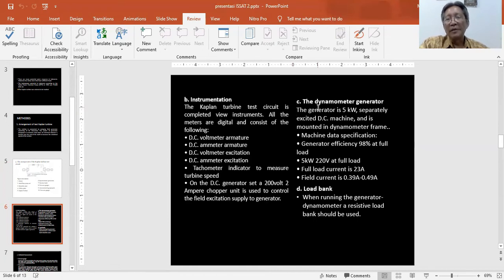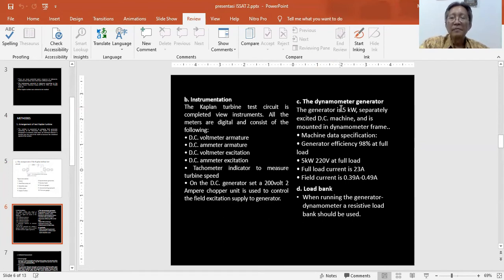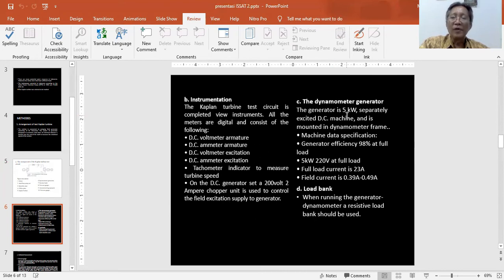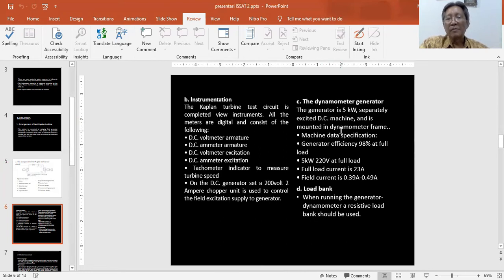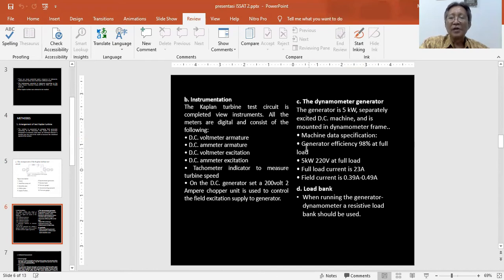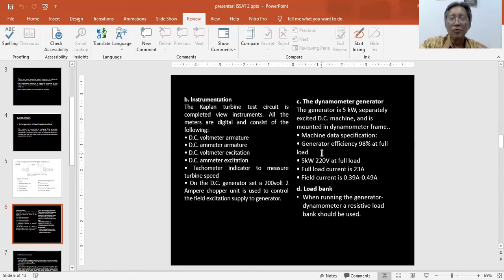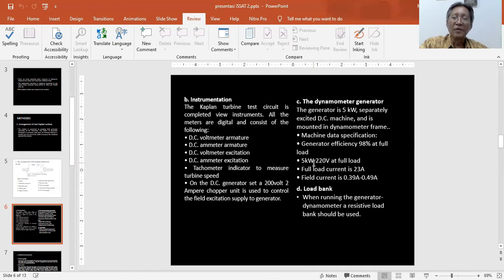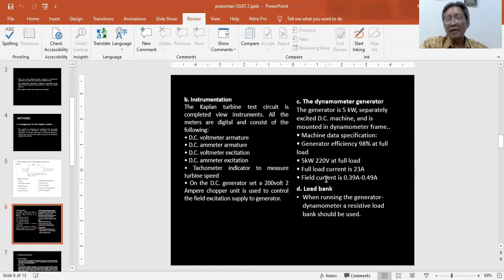The dynamometer generator is also set on the bearing frame. The generator is about 5 kW, separately excited DC, and is mounted in a dynamometer frame. Machine data specification: generator efficiency about 98% at full load, power 5 kW, voltage 220V at full load, full load current is 23 ampere with armature resistance about 0.59.